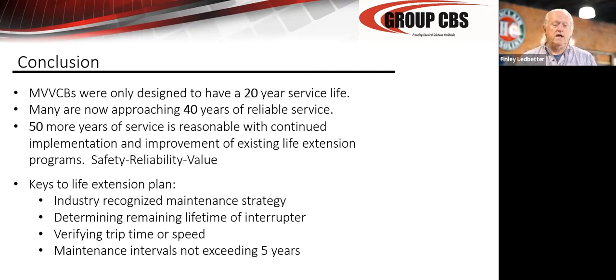Keys for the life extension, industry maintenance strategies. There again, pick someone you trust, pick their plan, work the plan. I'm going to tell you that I believe in the things that are in NETA. I had something to do with them. There are all kinds of maintenance strategies out there for this electrical equipment. Carefully review them, pick the one that fits you, your budget, and your plan. Obviously, a submerged arc furnace in a phosphorus plant, the maintenance on that is way different than the maintenance on a 15 kV dry type transformer in a big building. So it has to be subject to some criticality.